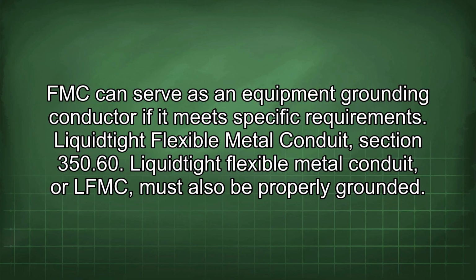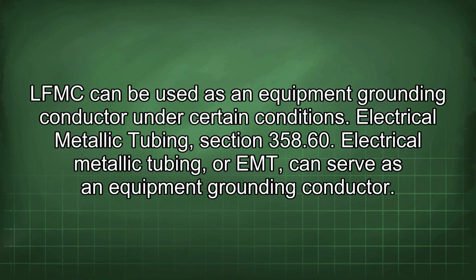Liquid-tight flexible metal conduit, section 350.60. Liquid-tight flexible metal conduit, or LFMC, must also be properly grounded. LFMC can be used as an equipment grounding conductor under certain conditions.